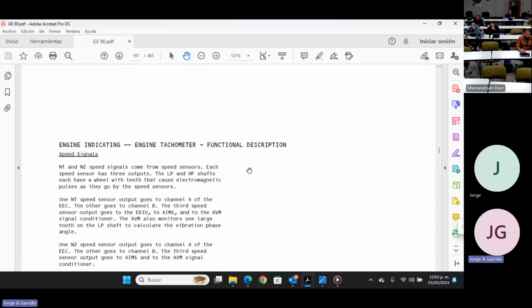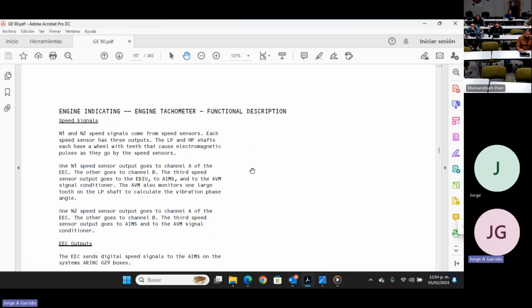So just as a reminder, the N1 and N2 speed signals come from the speed sensors. Each speed sensor has 3 outputs, and the LP and HP shafts each have a wheel with teeth that cause electromagnetic pulses as they go by the speed sensors. The N1 speed sensor output goes to channel A of the EEC, and the other goes to channel B. The third speed sensor output goes to the EDIU. So 2 channels are signaled inside the EEC for redundancy, and the third is used for communicating with other systems through the EDIU. Still, they all need to go through the EEC in order to have this EDIU supplied with the 429 data bus.